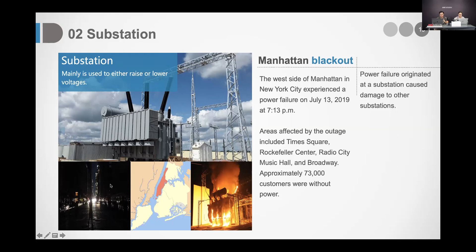So that's the substation situation. In the substation, we always want to monitor those primary equipments, like potential transformers, current transformers, circuit breakers, isolate switches, and surge arresters. I don't want to put too much detail here, but I want to give you the idea that all these crucial equipment have to be monitored, because 90% of the time failure happens because of temperature heating up. Another 10% is due to people's misconduct or misbehavior.